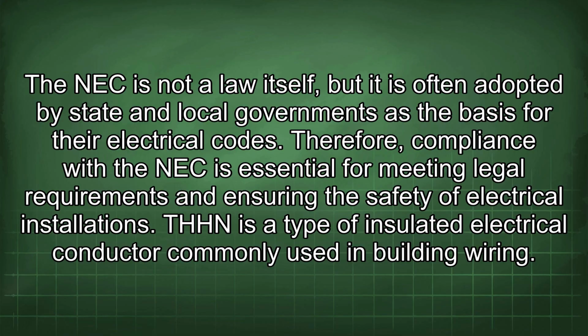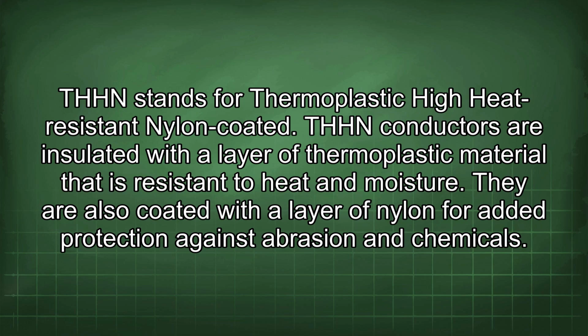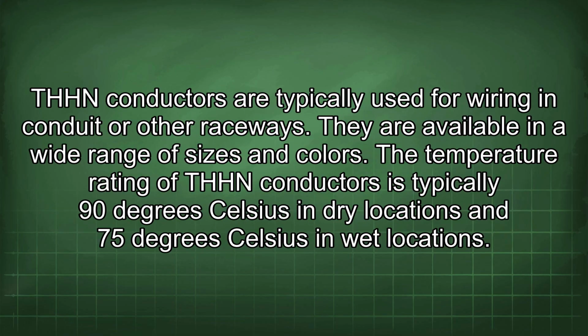THHN is a type of insulated electrical conductor commonly used in building wiring. THHN stands for thermoplastic high heat resistant nylon coated. THHN conductors are insulated with a layer of thermoplastic material that is resistant to heat and moisture. They are also coated with a layer of nylon for added protection against abrasion and chemicals. THHN conductors are typically used for wiring in conduit or other raceways. They are available in a wide range of sizes and colors. The temperature rating of THHN conductors is typically 90 degrees Celsius in dry locations and 75 degrees Celsius in wet locations.